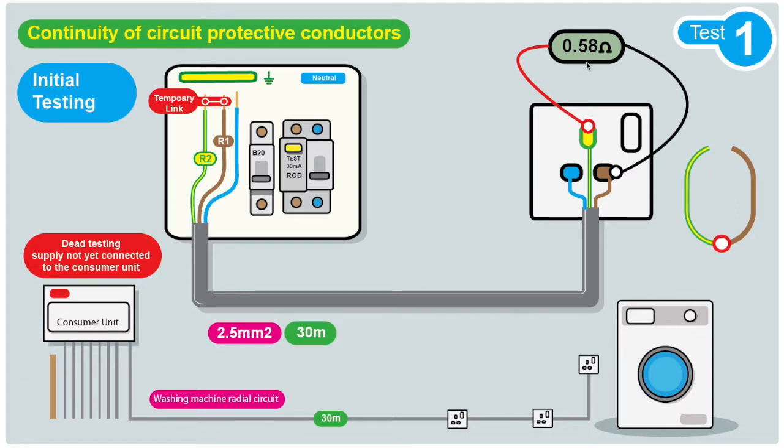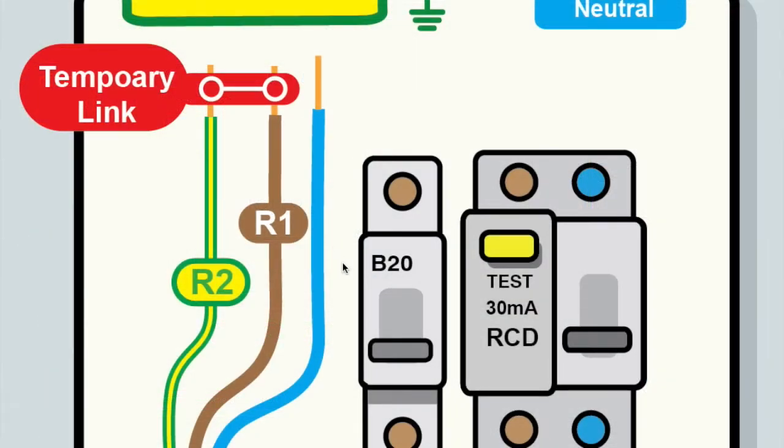We need to work out if that reading of 0.58 ohms is acceptable. It's shown that we've got continuity but it's only a number. We need to work out if that's an acceptable number. This is inside the consumer unit.